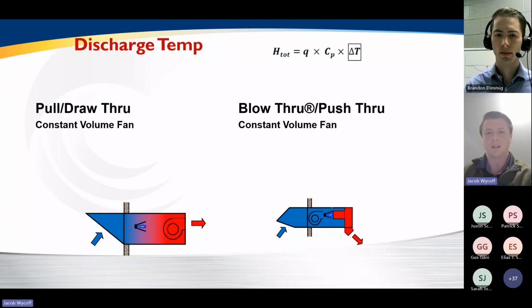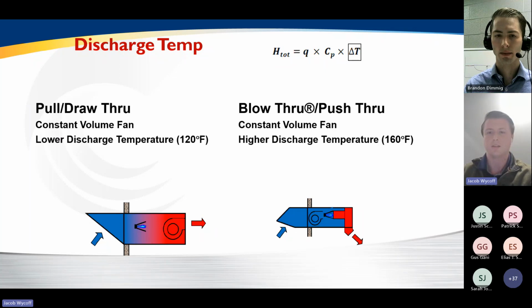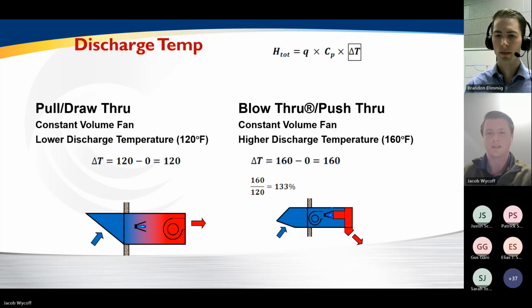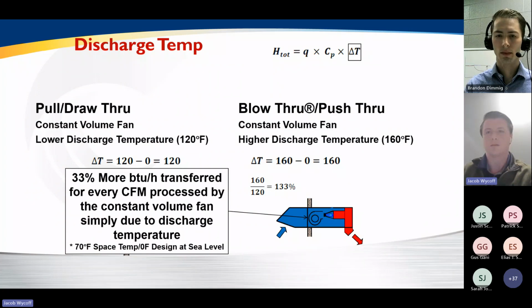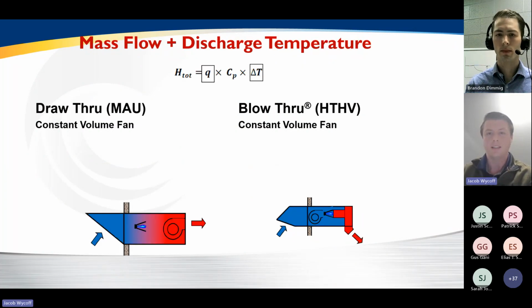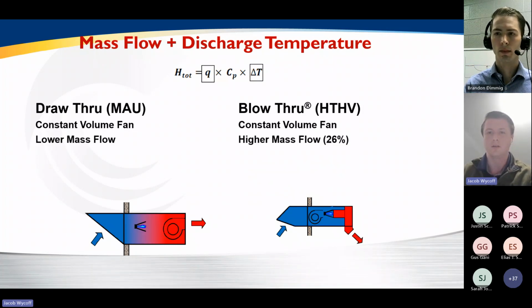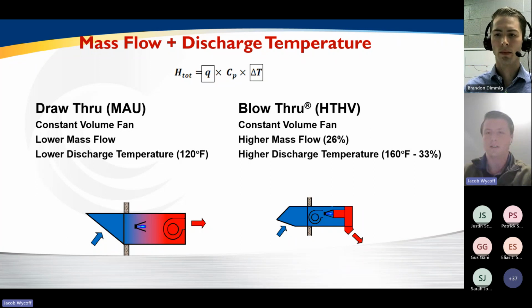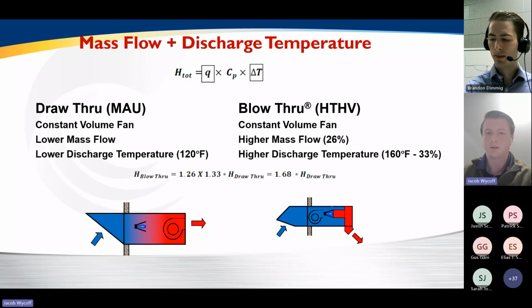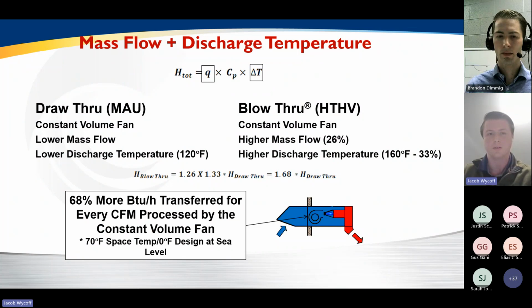Now, what about discharge temperature? We've already spoken about this. The difference in discharge temperature between 120 and 160 degrees leads to 33% more BTUs per hour transferred for every CFM processed by that constant volume fan, just simply due to turning up that discharge temperature from 120 to 160 degrees. When we combine these two effects, it adds up to an even greater difference. So we have the 26% more energy due to the higher mass flow, due to the higher density, and the 33% more BTUs due to the higher discharge temperature. Combining both of those effects, we get 68% more BTUs per hour transferred for every CFM processed by that constant volume fan.